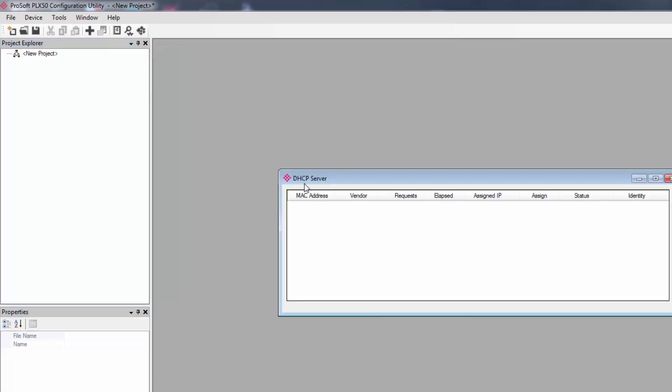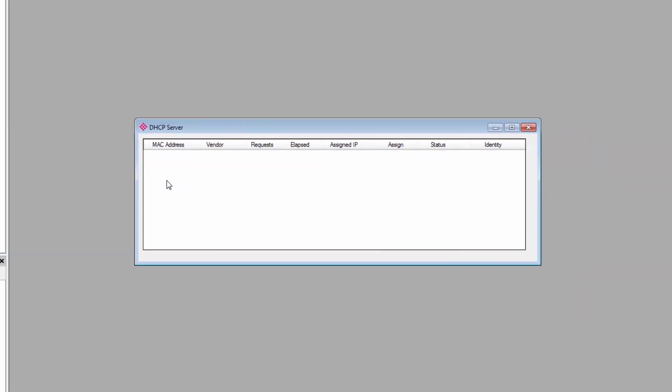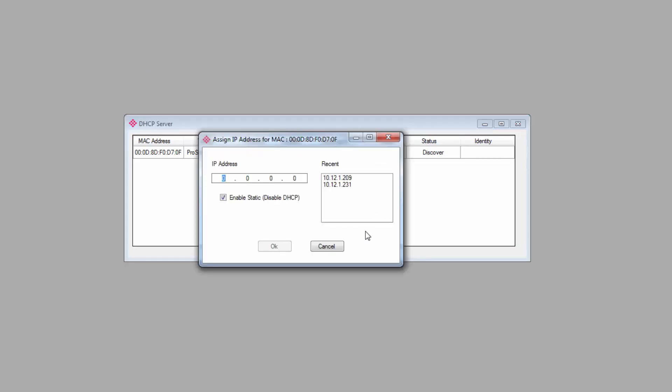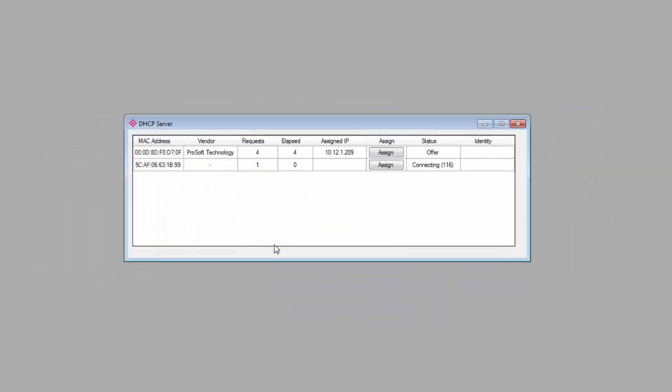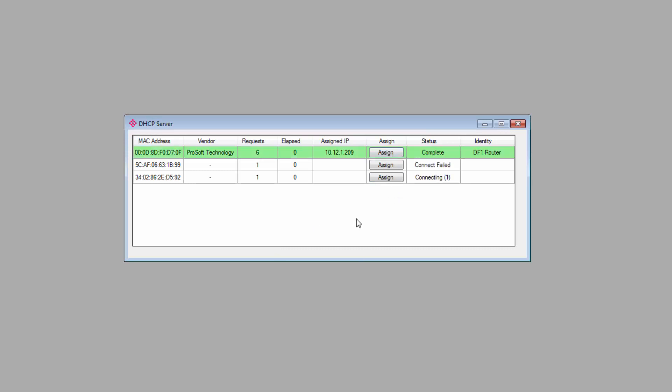The first time you connect the PLX51 to your network, you'll need to launch the DHCP server and assign it an IP address on your subnet. It's this button here in the menu bar, and there is our gateway. Click assign, and on the window that opens, I'll enter in an IP address that I know is available on the local network, and click OK. The bar should turn green. This lets you know that the gateway has accepted the IP address and is now connected. So we can close this window.